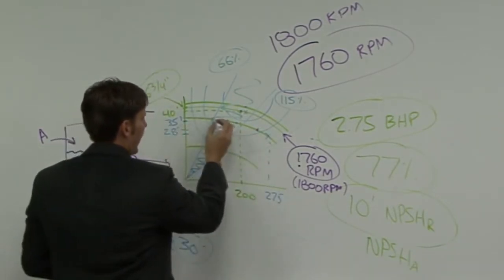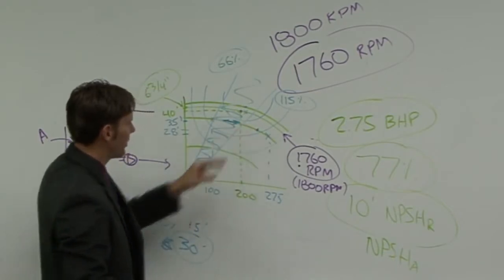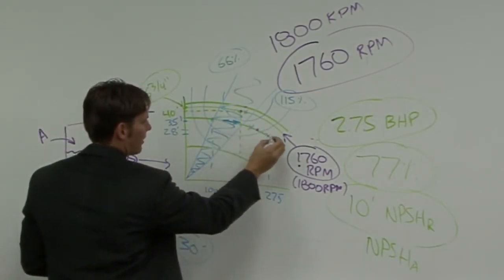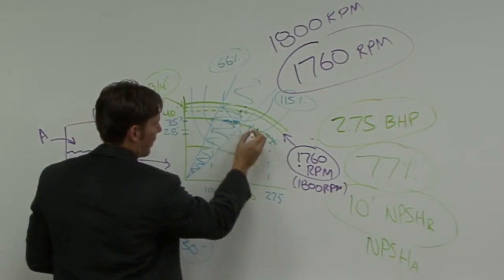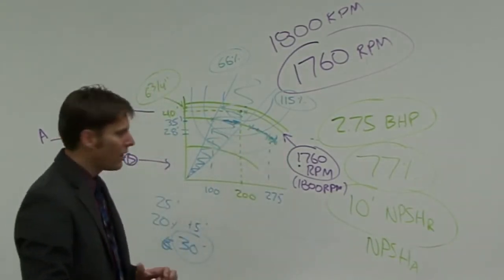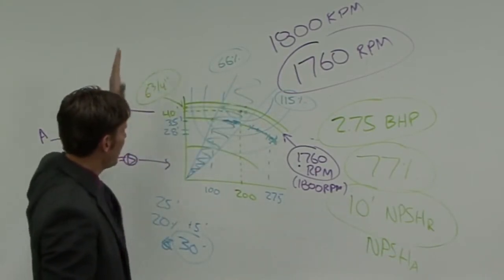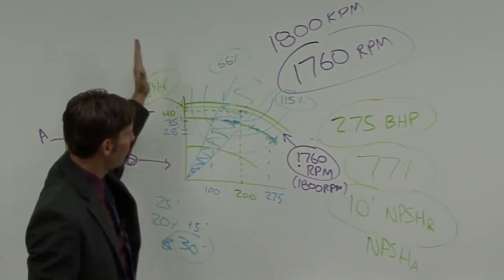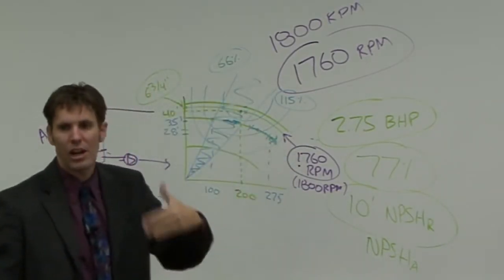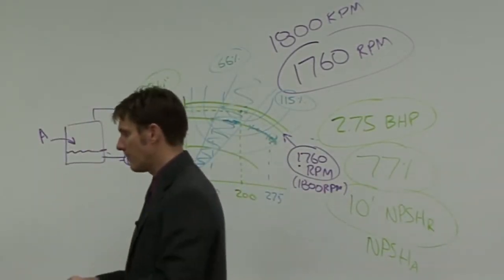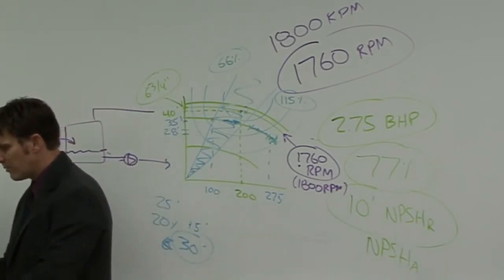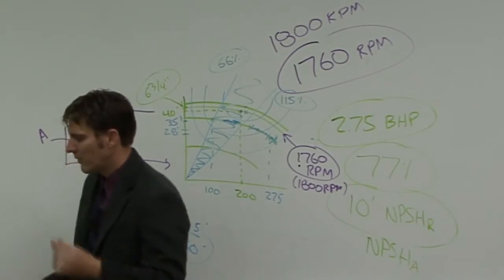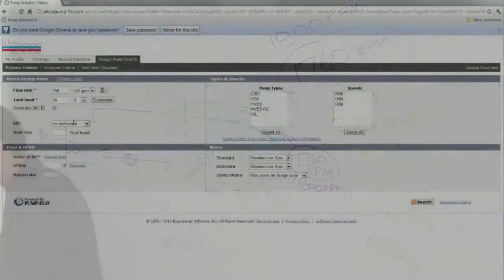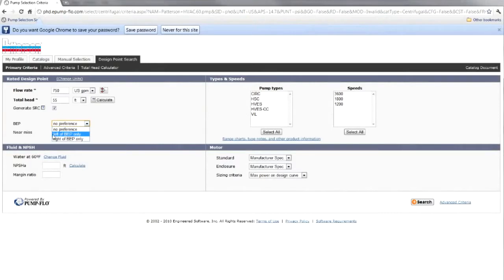So what it does is it could pull them closer to best efficiency point. But if they selected the pump out over here and then they lost their head pressure, it takes them further away from their best efficiency point. So that's why ASHRAE gives us more leniency to the left, because with the safety factors that are being used, it will pull us back, in reality, towards a higher efficiency point, not further away from it. So if you're going to do best efficiency point, it might be best to select left of best efficiency only. But honestly, I don't even do that, because I want to look at all the pumps that are available. The near miss, you can plug in what percentage you want of your head and how close that can be.